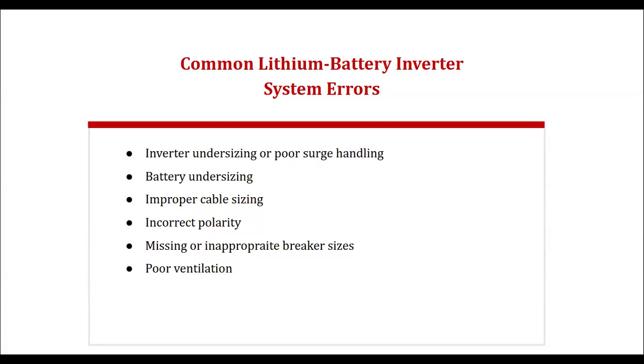Because when you load it and there's a drop along the battery cable, the battery will still be full when your inverter will be telling you that the battery is low. And then eventually there is an error. Because the battery is saying my capacity is high, and the inverter is saying no, the battery is low. So communicating, it will be showing funny errors. Just do what is proper. That's why you have standard sizes for all these things. A cable has a standard current capability, insulation breakdown value, and a lot more. So make sure you follow all these details while dealing with solar systems and lithium-ion batteries.